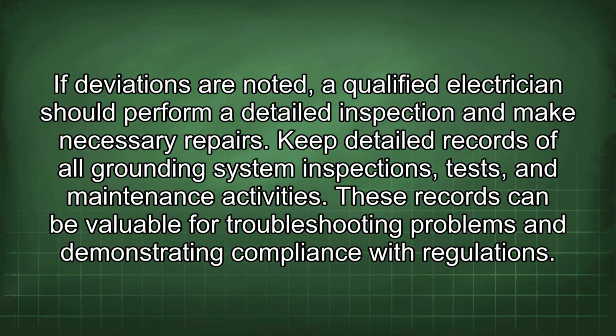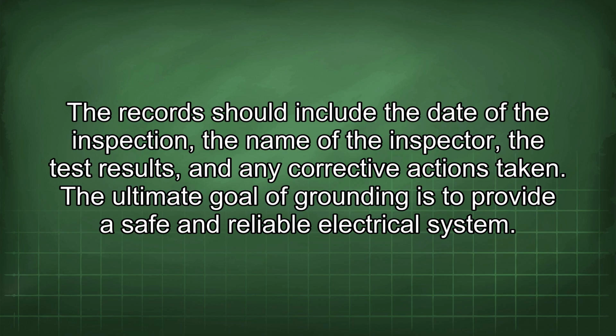Keep detailed records of all grounding system inspections, tests, and maintenance activities. These records can be valuable for troubleshooting problems and demonstrating compliance with regulations. The records should include the date of the inspection, the name of the inspector, the test results, and any corrective actions taken. The ultimate goal of grounding is to provide a safe and reliable electrical system.